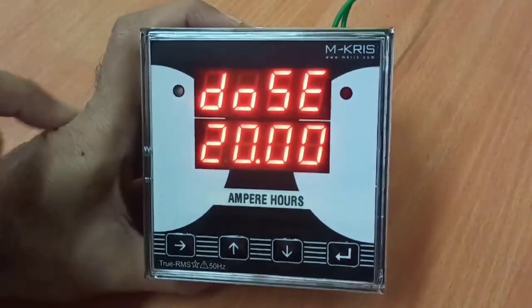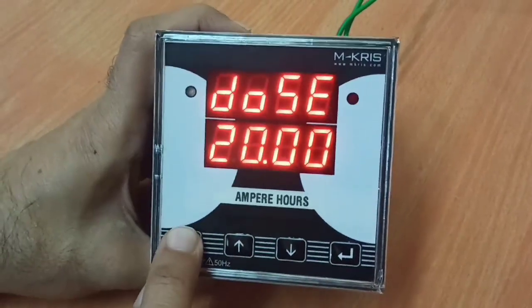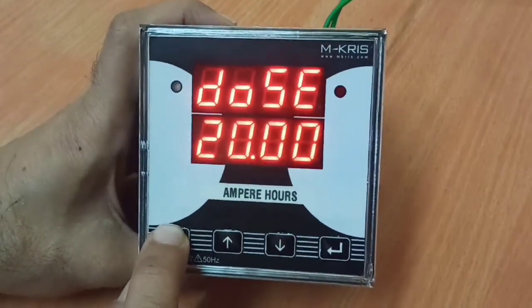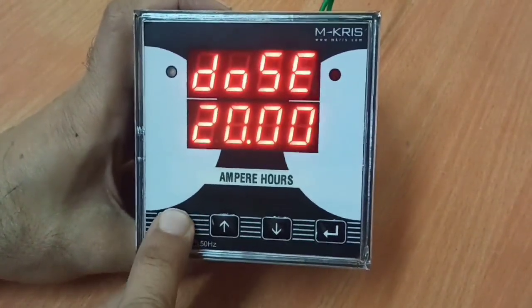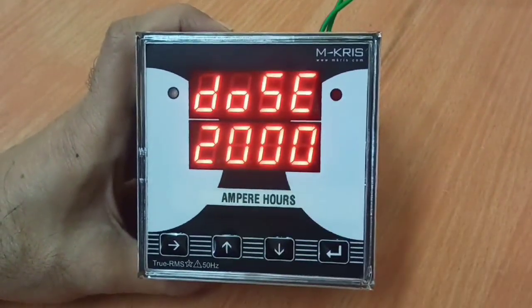Then we move on to the dose setting. This gives you the dose in Ampere Hour. Here, 20 Ampere Hour is given as the set value of dose. It can be changed using the menu button. A dosing value up to 9999 Ampere Hour can be fed here. If you don't want to use the dosing function, just type in 0000 — that will ensure the dosing function is disabled. The settings are saved and you are reverted back to the normal display.